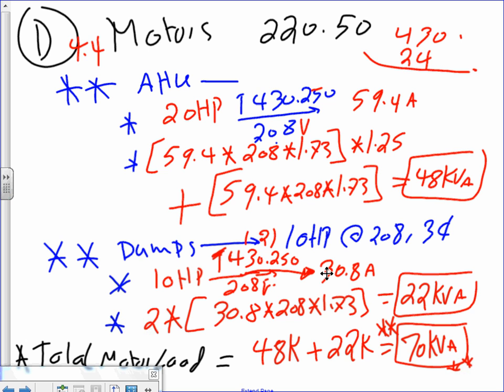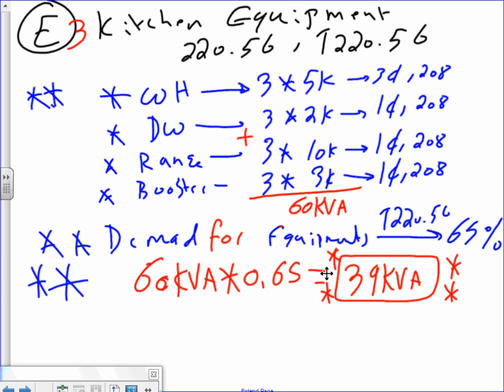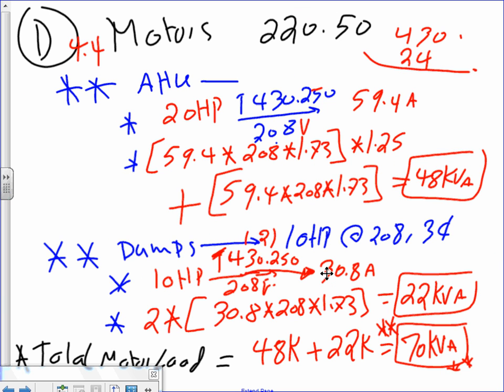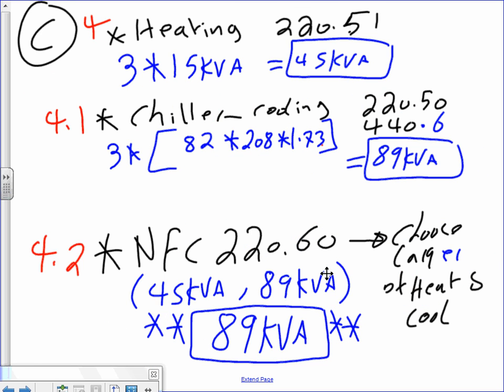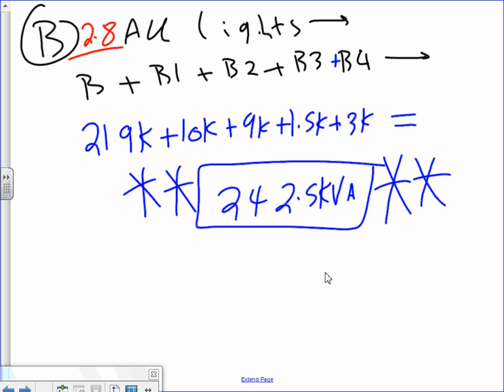Okay. Then we went to the motors, and we came up with a size of 70 kVA. For the lights, set 2.5. We're down at 242.5. For lights, let's go back to the lights. All lights, 242.5. What did they say? I thought you said 2.5 first. I could have just misheard you. You could, we can rewind.